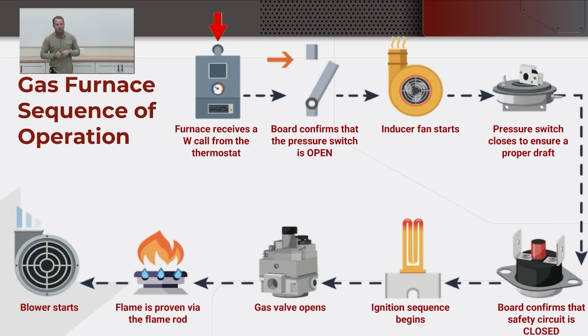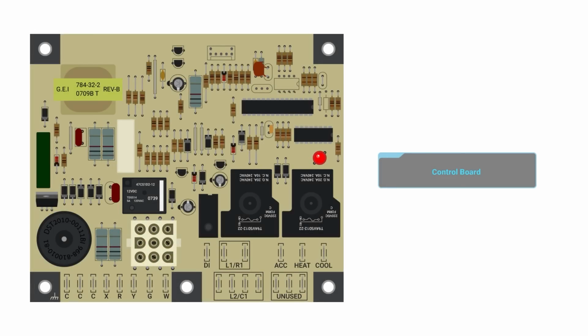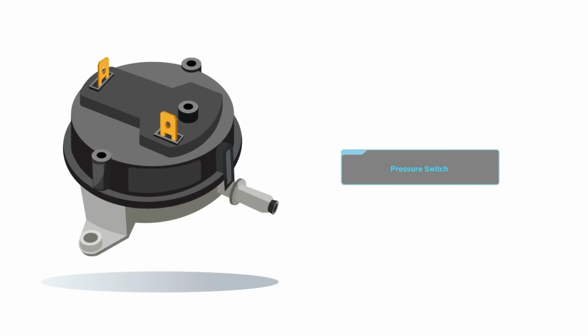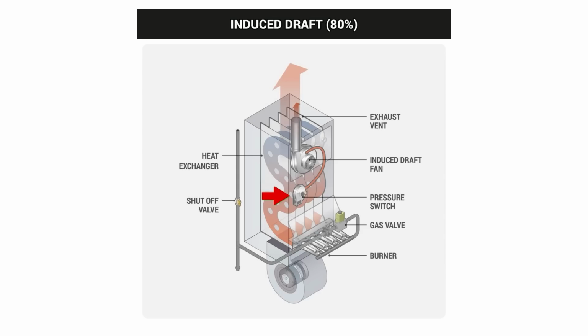You don't have a call on O in a typical heat pump, but I digress. In a gas furnace, generally, when you go into heat, it's just a W call. W calls, next thing happens, the board confirms that the pressure switch is open to start with. This is really key, because this will happen sometimes. Your actual flue pressure switch, your inducer pressure switch, whatever you want to call it, the pressure switch that confirms that you have an operational inducer fan, it has to start open, and then it goes closed.